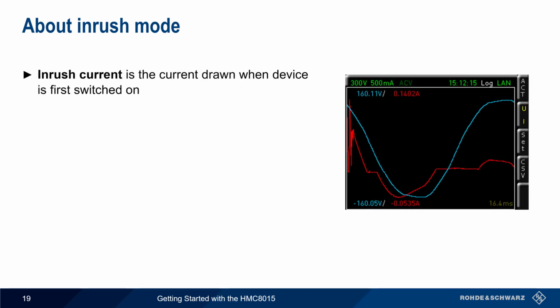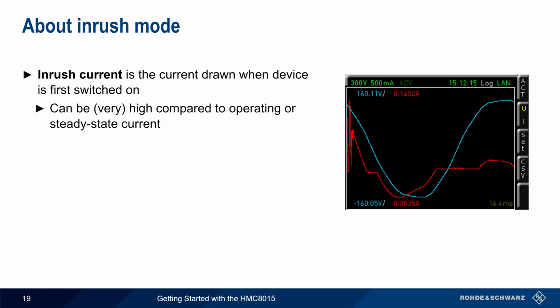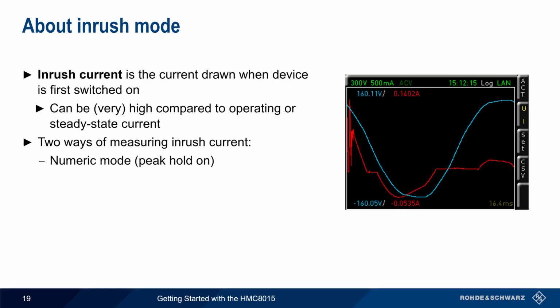Compared to Trendchart mode, Inrush mode is concerned with much shorter events. This is because inrush current is defined as the current that's drawn when a device first powers up or is switched on. This current can be very high compared to the current drawn during steady-state operation. There are two ways of measuring inrush current with the HMC. The first of these is using peak hold while in numeric mode. The second is in inrush mode.